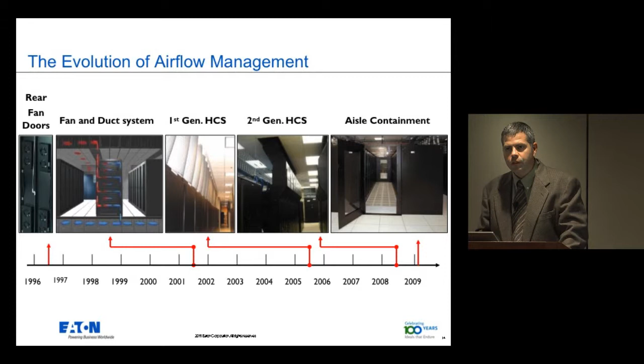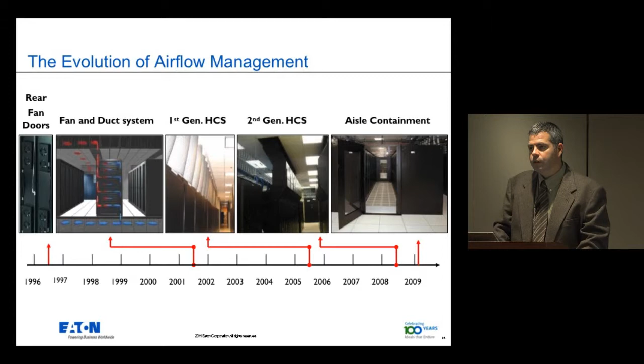We see more and more adoption of it, so that you can separate the cold, you can keep the cold air in front of the servers, and you can take the hot air and bring it back to the CRAC units directly. Or nowadays, there's a session on the ASHRAE guidelines, I think, this week, and a lot of people are moving away from CRAC units. They'll just move to building-size economized systems, with either air-side economizer or water-side economizer. We're starting to see people move away from even putting in CRAC units. As the pressure is to lower the PUE, and based on those pie charts we saw before, people are trying to eliminate CRAC units altogether. And with the new ASHRAE guidelines, it's feasible to do so.